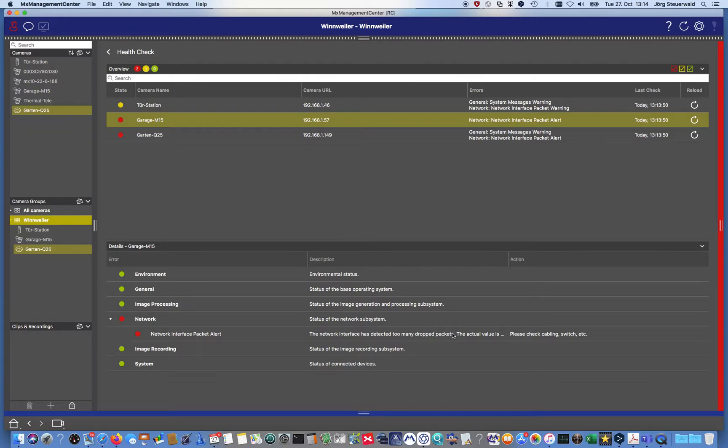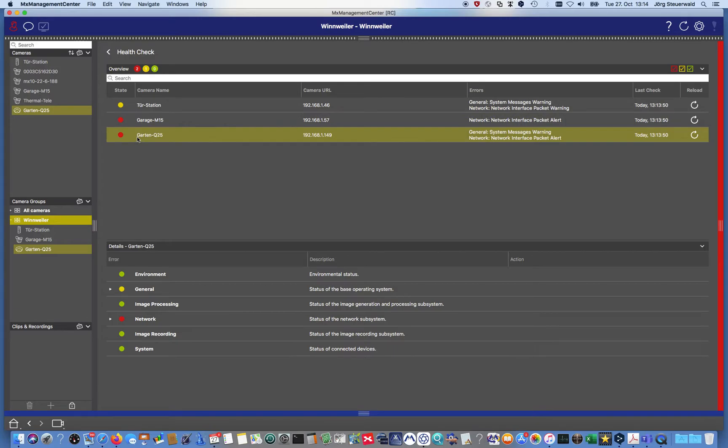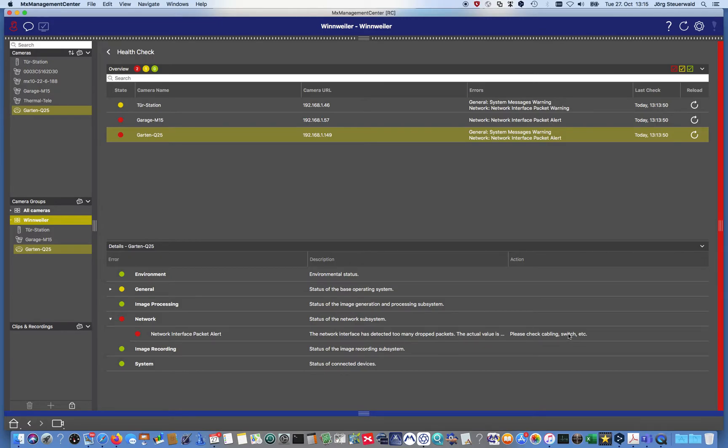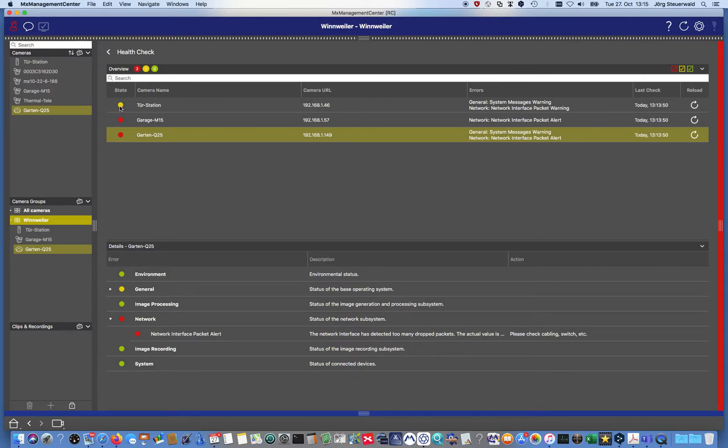Maybe the switch has a problem because I have another camera which also has an error message there. I click on that. This camera has a warning and an error. Checking the error, it means as well too many dropped packets. Check cabling, switch. Maybe the switch has an issue because the two cameras have a cabling issue. That's maybe not so realistic, but both cameras are connected to the same switch. Then maybe we need to check the switch if it has some issues.